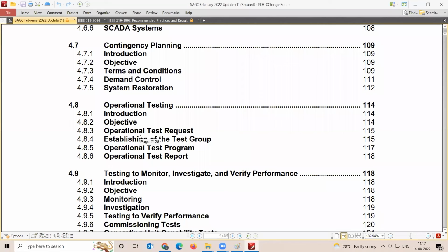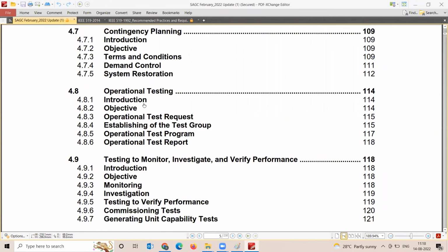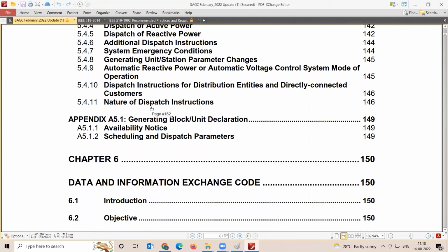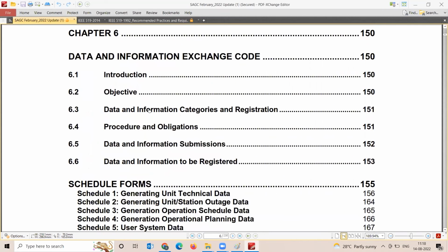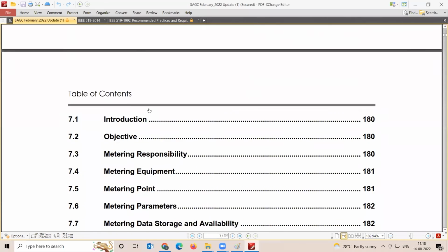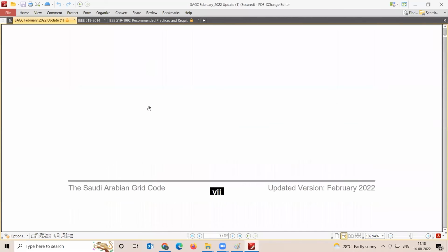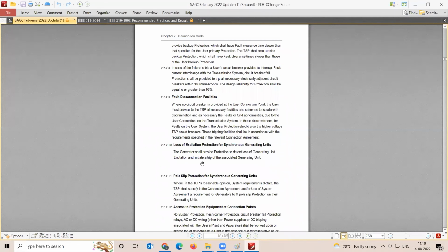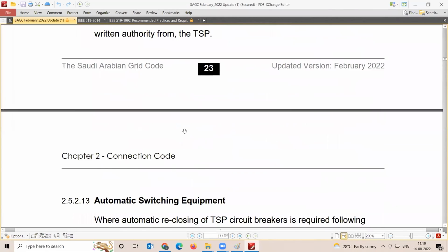And you might be aware of R1 and R2 testing in the Australian market, where something has to be tested at site and proved within plus or minus 5% error with respect to the simulation they have made. All these things have to be part of the grid code, though they may not be needed as long as the grid is strong and considerable renewable penetration is not there in the market. This also gives the protections needed.